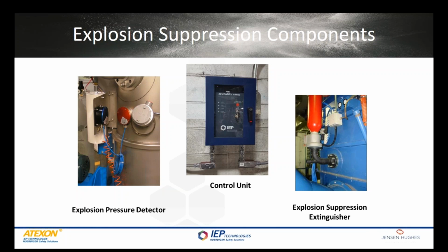The main components of an explosion suppression system, very similar to a fire suppression methodology, are detection, control, and extinguishers. The detectors are typically pressure-activated detectors that can either be static detectors that would look for a specific programmed or calibrated detection set point, or they could be rate of rise detectors that are looking for a specific rate of pressure increase that would be synonymous with an explosion from that hazard within that volume vessel.